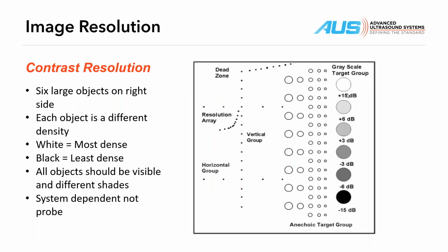Well, contrast resolution is not frequency dependent. You should be able to see all 6 objects, whether you're using a 1 megahertz probe or a 15 megahertz probe. So this is really system dependent, not frequency or probe dependent. So for contrast resolution, you only need to evaluate it using 1 probe. Keep that in mind, but it is a test and should be part of your printouts that you conduct during any preventative maintenance you're performing. This is one of the ways that you can determine degradation over time. And we'll talk more about that in a couple minutes.